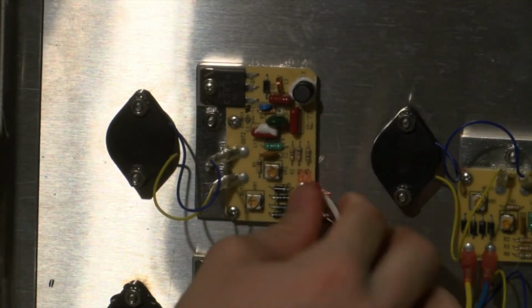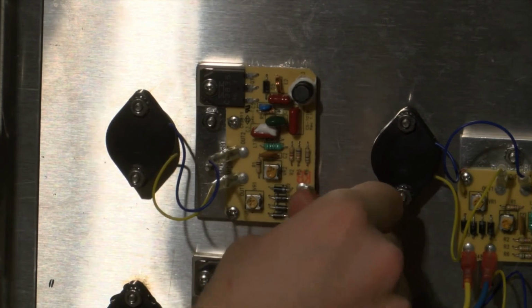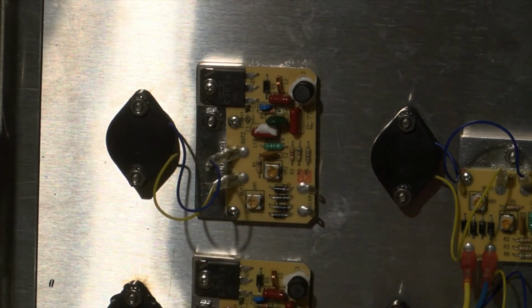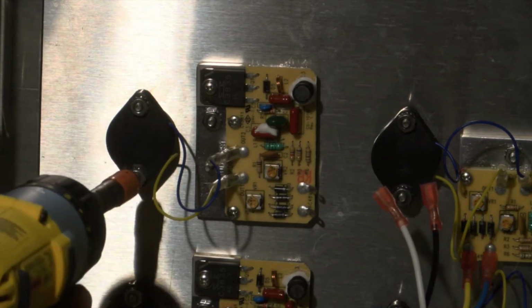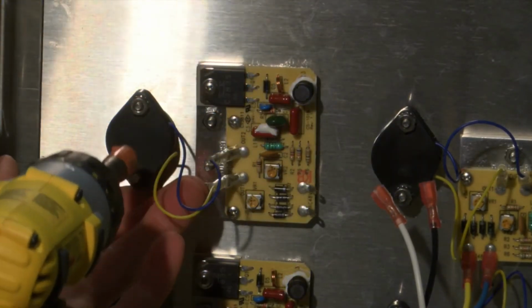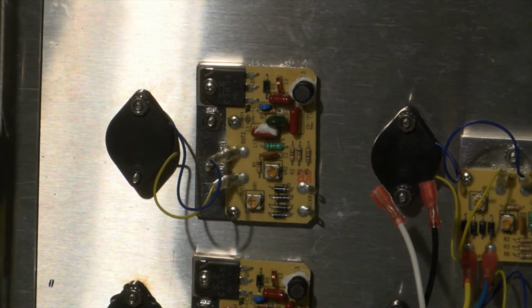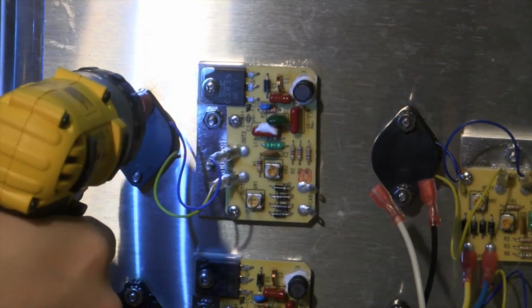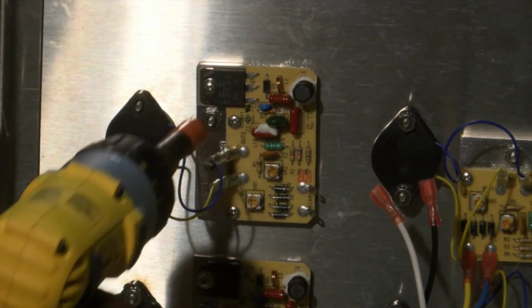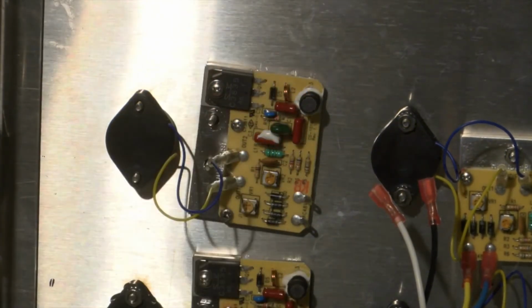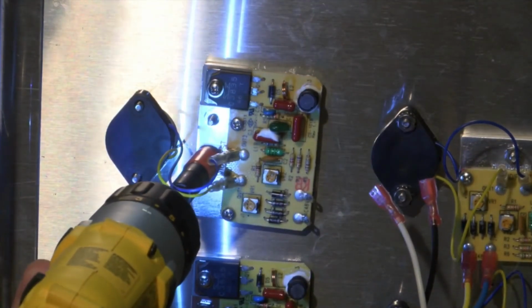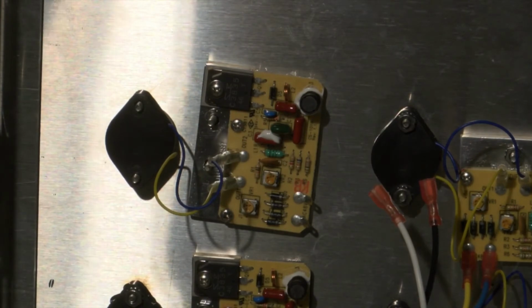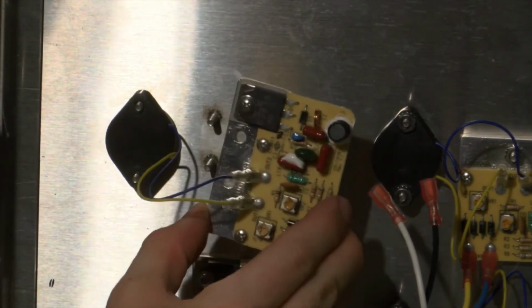First, remove the 2 daisy chain wires from the circuit board, and then you can remove the transducer and circuit board. Simply unscrew the 2 screws that hold the transducer on, and the 2 screws that hold the circuit board on. You can then remove the circuit board and transducer completely.